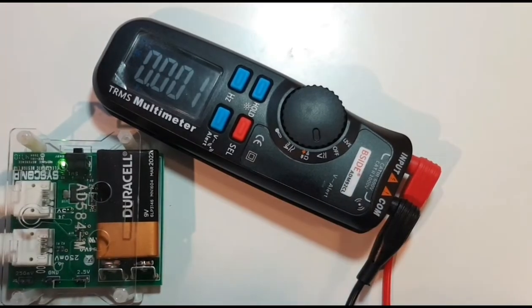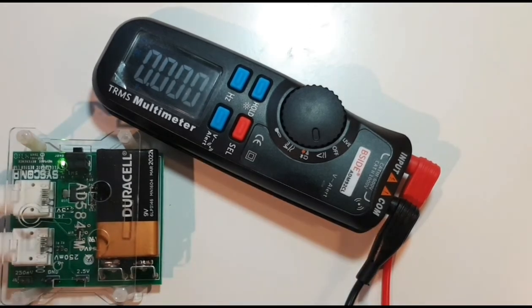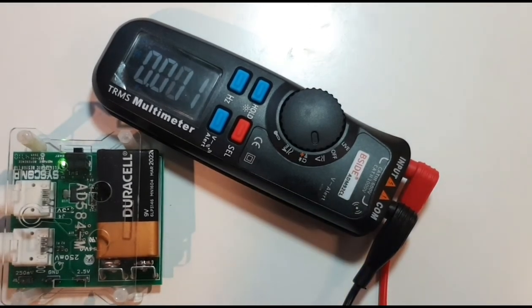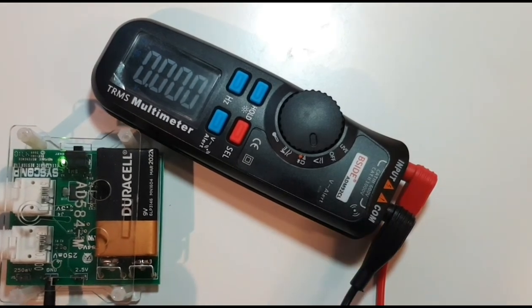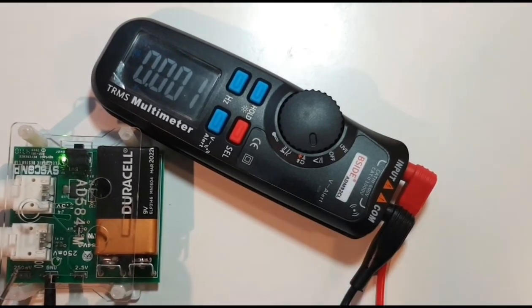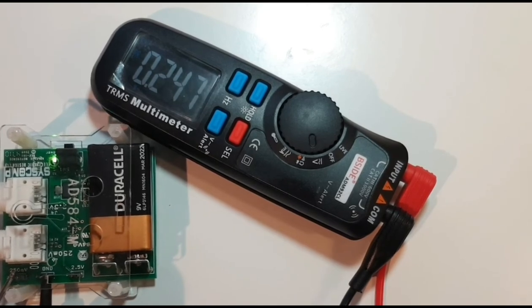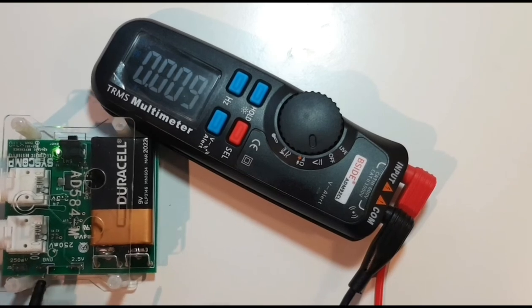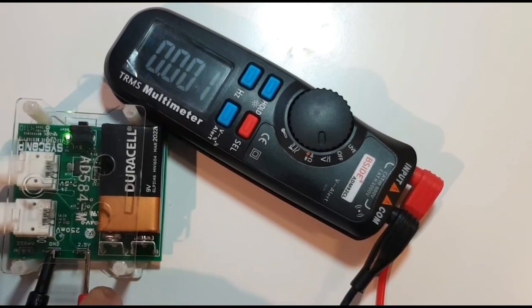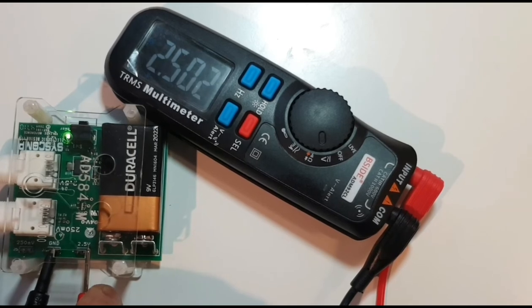We're going to do a quick voltage accuracy test. We have it in volts DC mode. And I will hook it up to the precision voltage tester. We're at the 250 millivolt level. Looking pretty good. Now we'll try the 2.5 volts. Not bad, not bad at all.